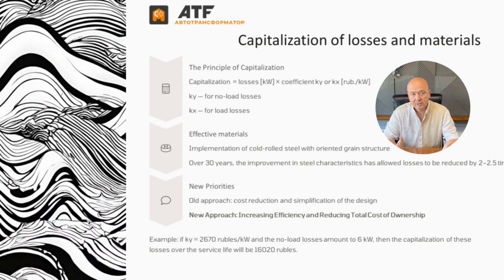Each loss type is assigned a capitalization rate. For no load losses, a coefficient known as KY. For load losses, a different one, KX. The capitalization is calculated as losses in kilowatts multiplied by the respective coefficient in currency per kilowatt. For instance, if KY is 2,670 rubles per kilowatt and the no-load loss is 6 kilowatts, then the capitalized value of those losses over the service life would be 16,020 rubles.